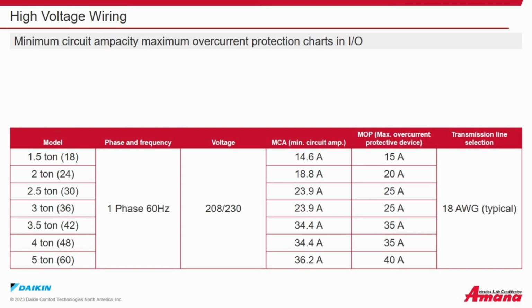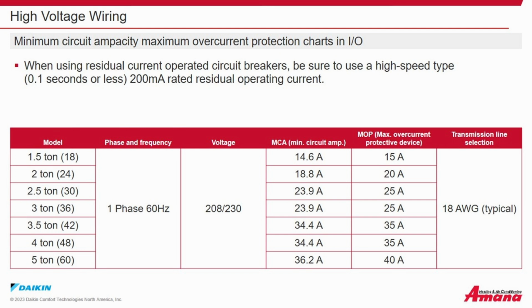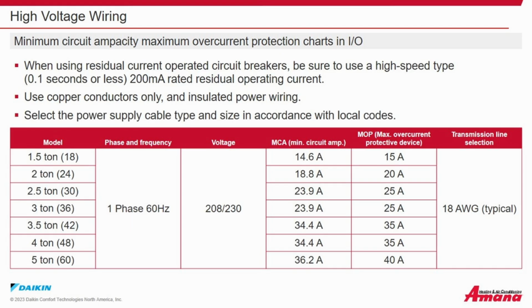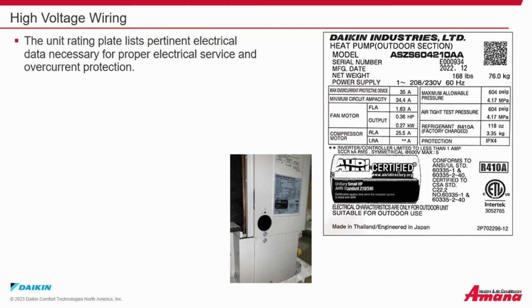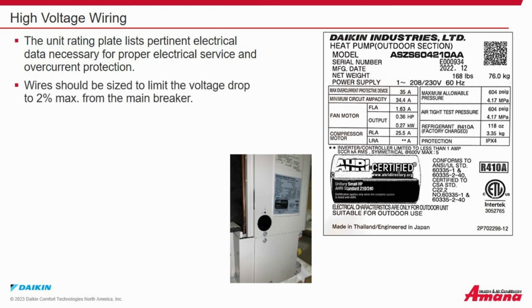High voltage wiring. Below are the minimum circuit ampacity and maximum overcurrent protection charts from the installation and operation manual. When using residual current operated circuit breakers, be sure to use a high-speed type, 0.1 second or less, 200 milliamp rated residual operating current. Use copper conductors only and insulated power wiring. Select the power supply cable type and size in accordance with the local codes. The unit rating plate shows a list of pertinent electrical data necessary for proper electrical service and overcurrent protection. Wires should be sized to limit the voltage drop to a maximum of 2% from the main breaker.